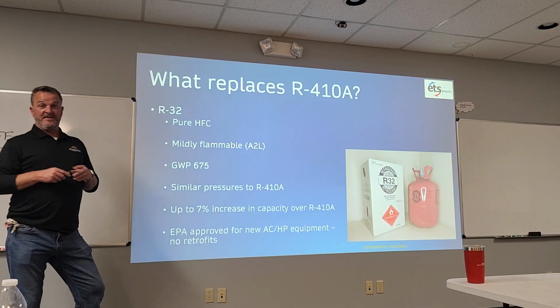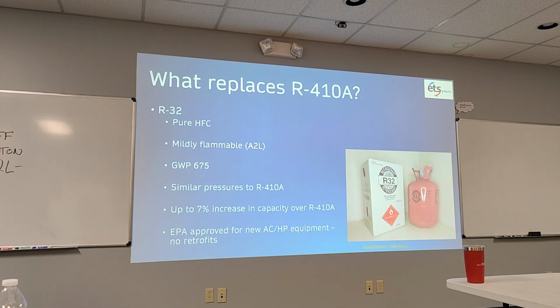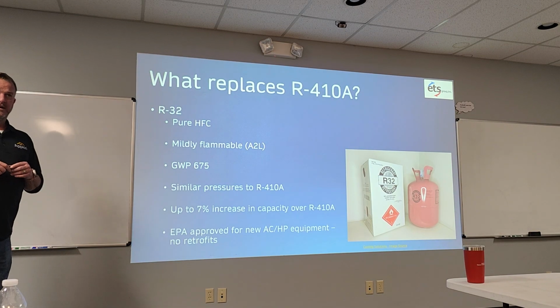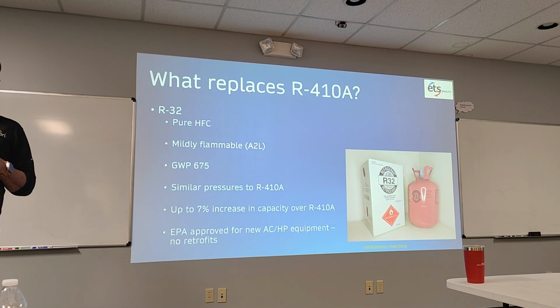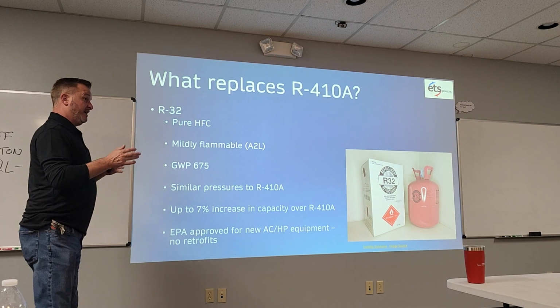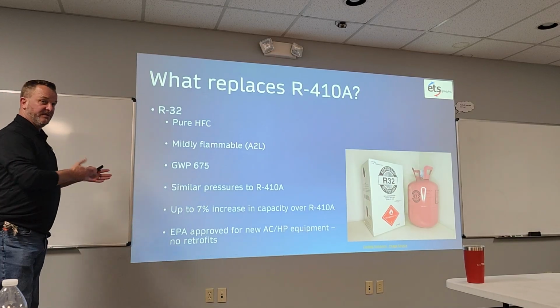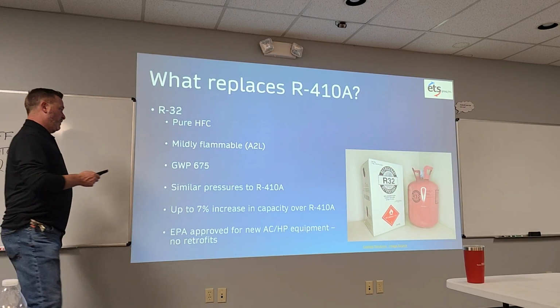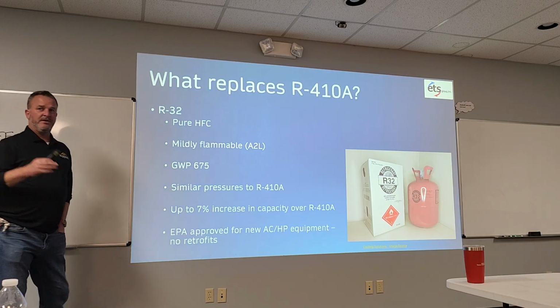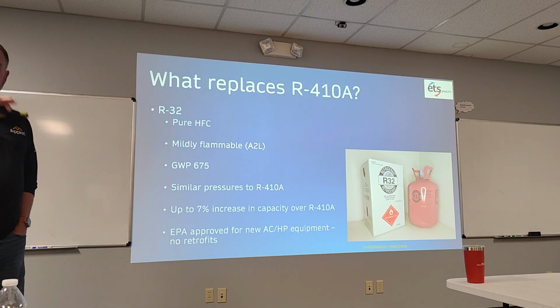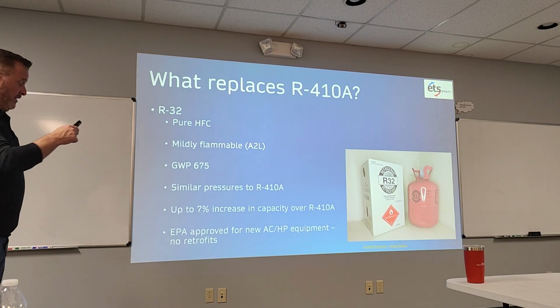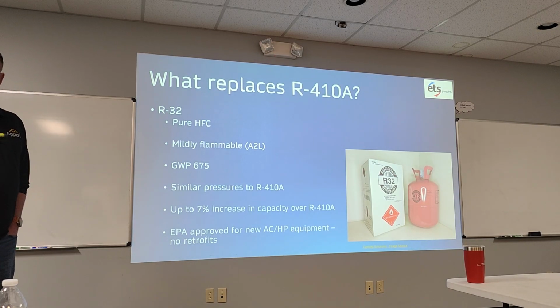So we've got a GWP of 675, alright? And the one thing I've found out over the last couple of months - I know a couple guys who are really big in the refrigerant market, know a lot of stuff - I was starting to hear that as of 2030, there's a regulation put in place that all refrigerants have to be below 600 GWP in order to move along, and that was kind of that threshold. So that's why a lot of the other OEMs and manufacturers went to 454B, which I'll show you in a second, because they're saying well this is 675. As of 2030, the regulation says it has to be under 600 in order to keep using it. Well, that's complete hogwash. There's no such regulation out there.